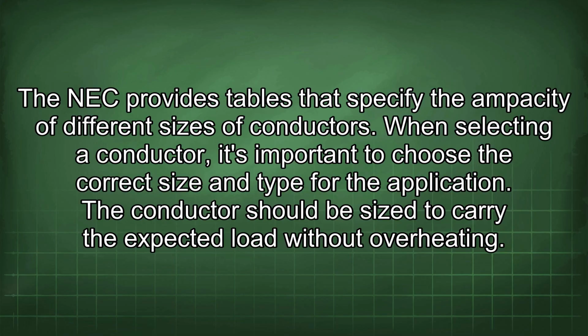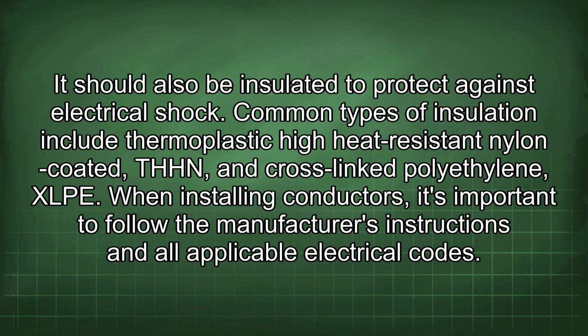When selecting a conductor, it's important to choose the correct size and type for the application. The conductor should be sized to carry the expected load without overheating. It should also be insulated to protect against electrical shock. Common types of insulation include thermoplastic high heat resistant nylon coated (THHN) and cross-linked polyethylene (XLPE).